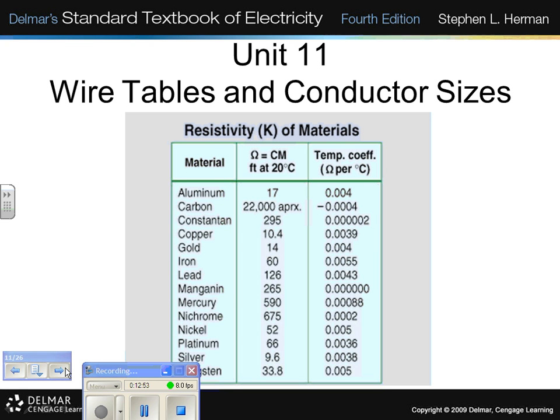So we're going to be using 10.4, and I'm not even going to talk about aluminum, because what does it say in the code book, by the way, about copper or aluminum? It says all calculations are copper unless stated otherwise. When you do any kind of a course where it's code, all the questions, even the California State Inspector's License examination, says on the test, all questions refer to copper unless stated otherwise.